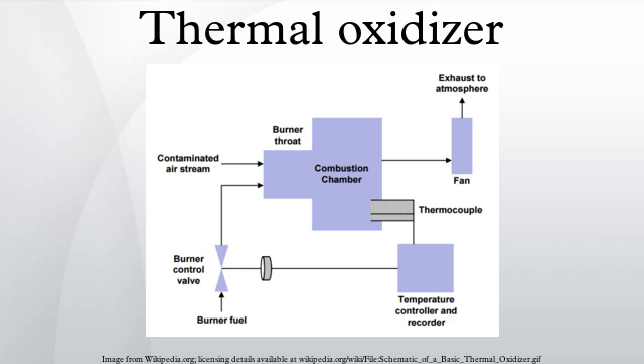Most systems operate within the 260 degrees Celsius to 1000 degrees Celsius range. Some systems are designed to operate both as RCOs and RTOs. When these systems are used special design considerations are utilized to reduce the probability of overheating, as these high temperatures would deactivate the catalyst, for example by sintering of the active material.